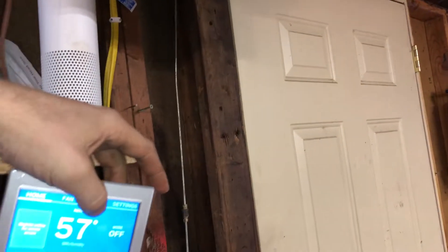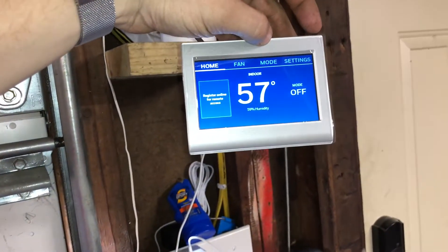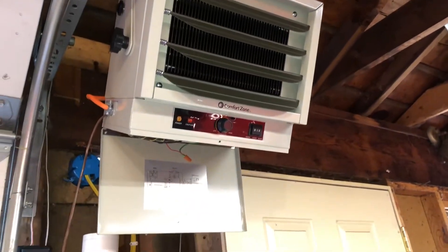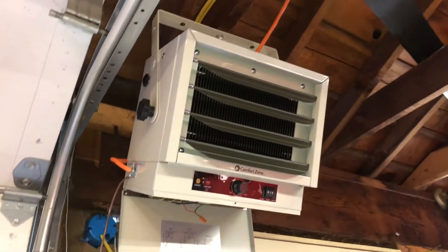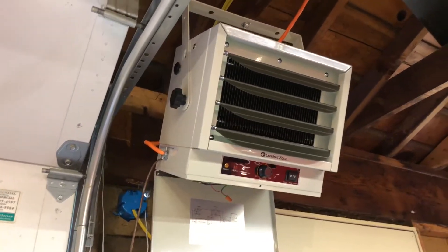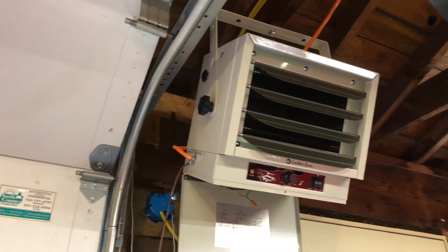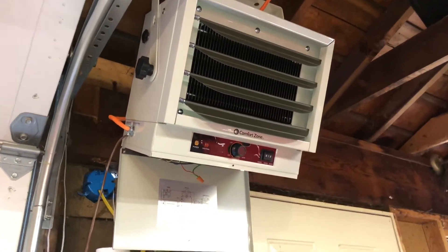So right now if I go into my thermostat and I turn it to off, my contactor opens and the heater shuts off. Very, very cool. I just wanted to show you guys that because I couldn't find anything online that mentioned somebody doing this, and I think it's a really cool thing to be able to do. These heaters are great — they produce a lot of heat for how much they cost, they're pretty compact, and they're really versatile with the ability to control them with a thermostat. I'm not a licensed HVAC technician, I'm not an electrician, so please do any of this at your own risk. But this is what I did in my garage and it's working beautifully. Thanks for watching.